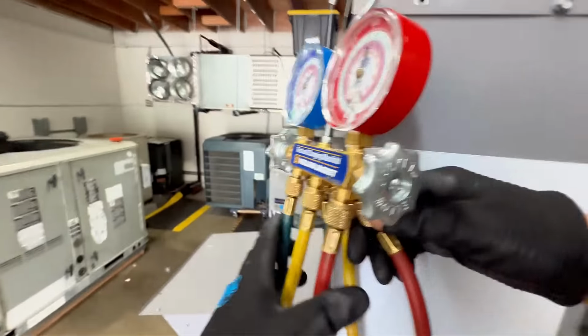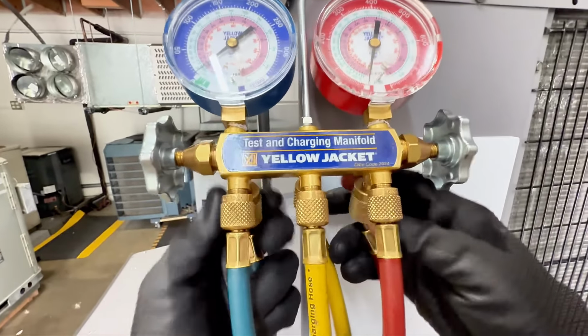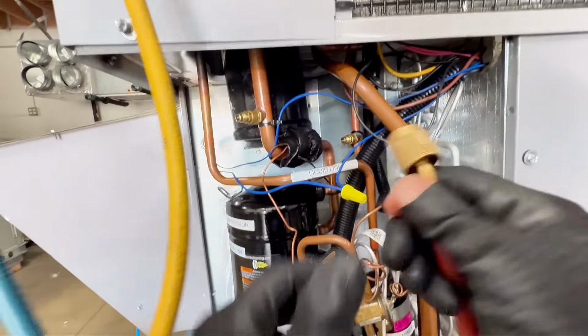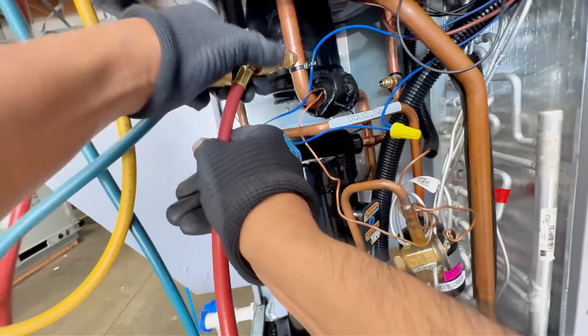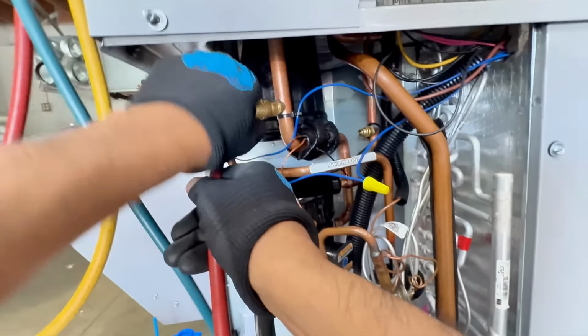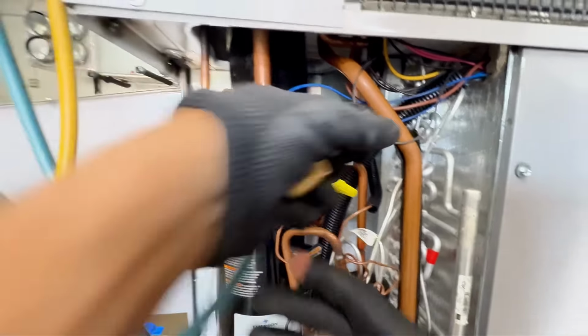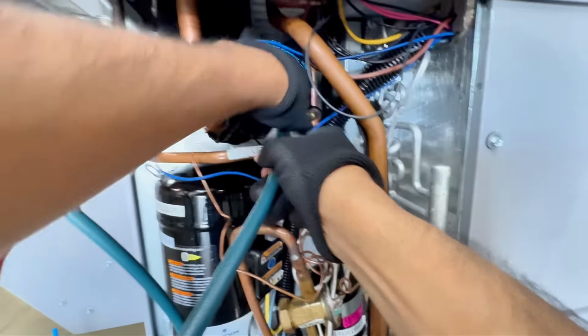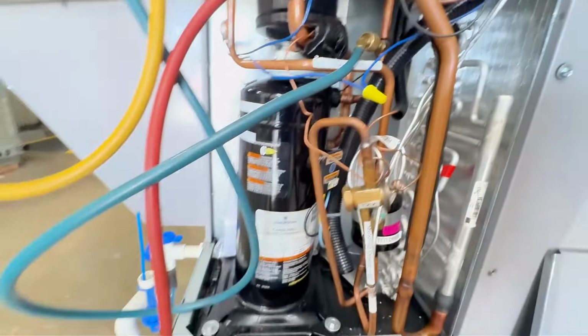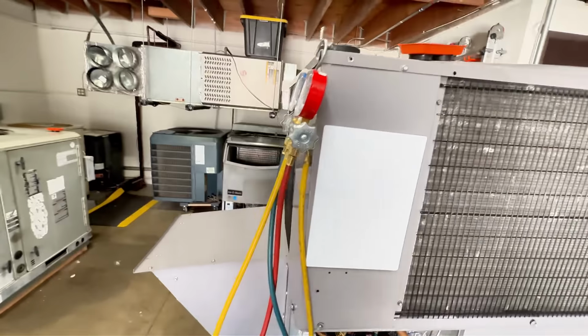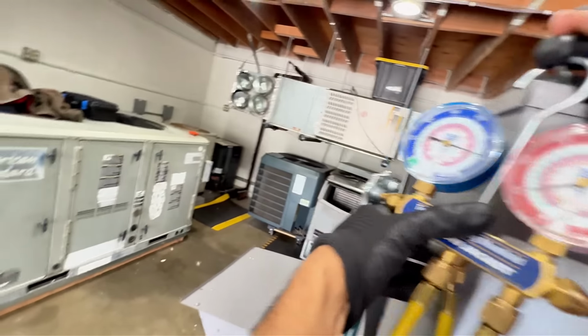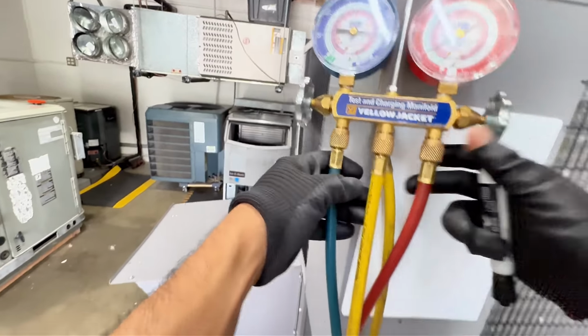Now I am gonna check pressures. I do have these low loss fittings. You definitely want to use low loss fittings. It's 410A. 410A is higher pressure, so I'm gonna go ahead and connect that there. Okay, and connect the low side. And technically, you do want to wait 5 to 10 minutes. You don't have to wait forever, but you do want to wait a little bit.